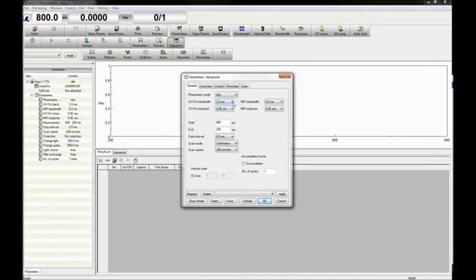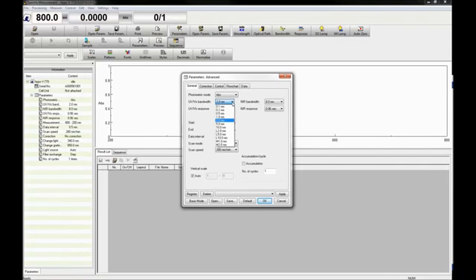If you are using a V730, the bandwidth remains fixed at 1 nm. The V750, 760, 770, and 780 all allow for the bandwidth to be varied.